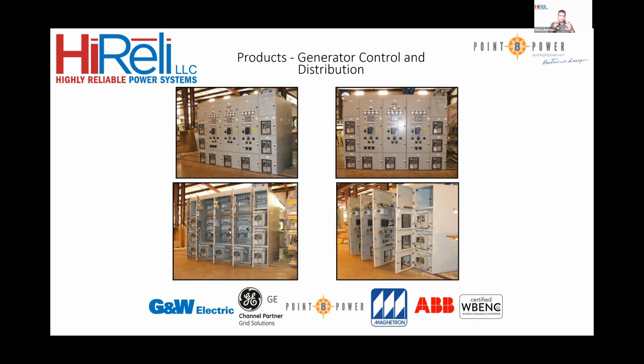So these pictures just show you a typical piece of gear that has all the control systems in place. So let's talk about arc resistance. Point 8 is very unique in the fact that they can provide solutions for arc resistance, low voltage and medium voltage. Low voltage, going up to 85 kA for 100 milliseconds, and medium voltage going up to 63 kA for 500 milliseconds. Obviously, it's limited to 15 kV and 4,000 amps.